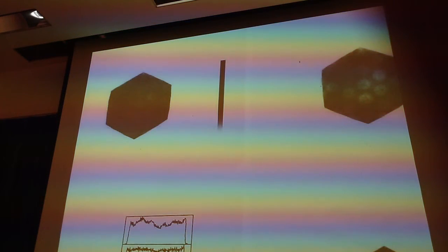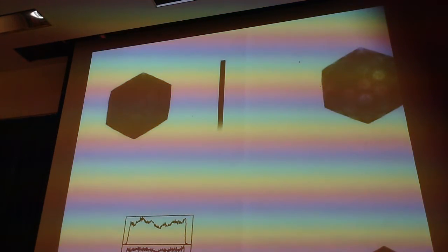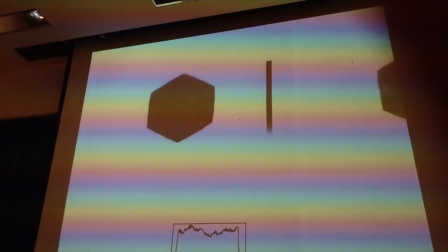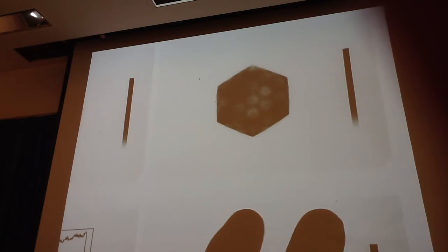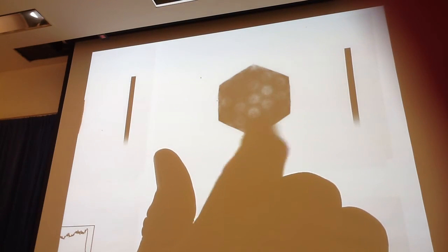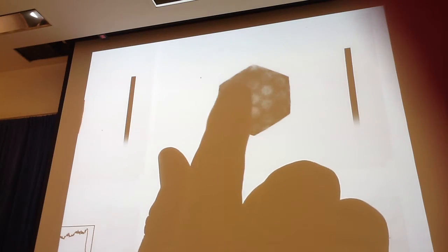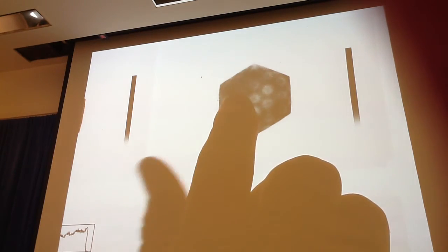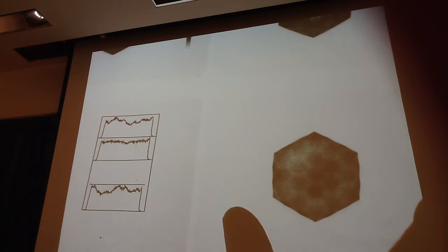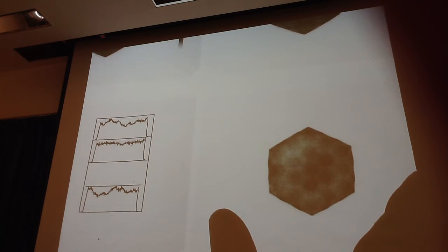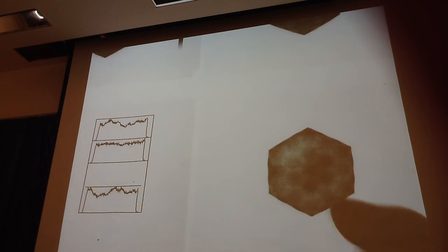And when you have what they call an annual PM, or preventative maintenance, then what they do is they'll individually tune each of the PM tubes. So the ones that are all white here are good. The ones that are black, those are the ones that are out of tune. We look at this image here, and this image here, and it shows you the ones that are probably needing some correction. What they do is they adjust the voltage.